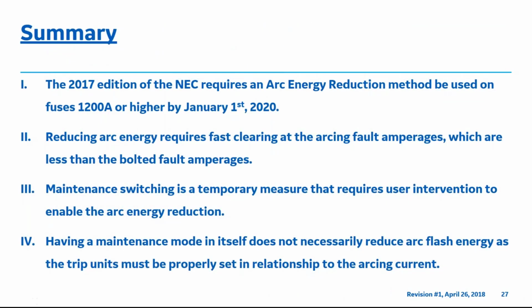To help summarize this presentation, line item number 1, the 2017 edition of the NEC requires an arc energy reduction method to be used on fuses 1200 amps or higher by January 1st, 2020. Line item number 2, reducing arc energy requires fast clearing at the arcing fault amperages, which are less than the bolted fault amperages. Line item number 3, maintenance switching is a temporary measure that requires user intervention to enable the arc energy reduction. And line item number 4, having a maintenance mode in itself does not necessarily reduce arc flash energy, as the trip units must be properly set in relation to the arcing current. This concludes the technical content of this presentation.